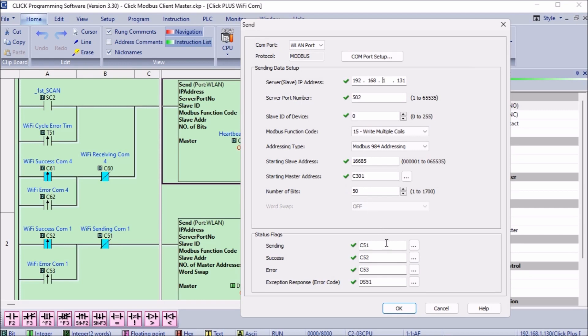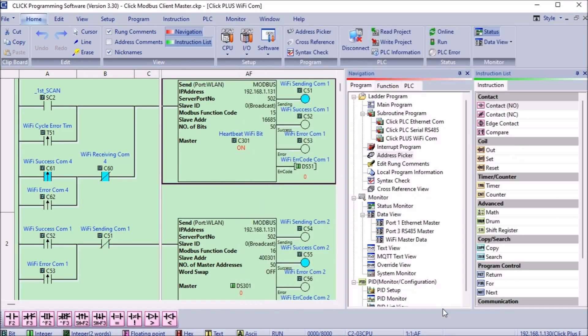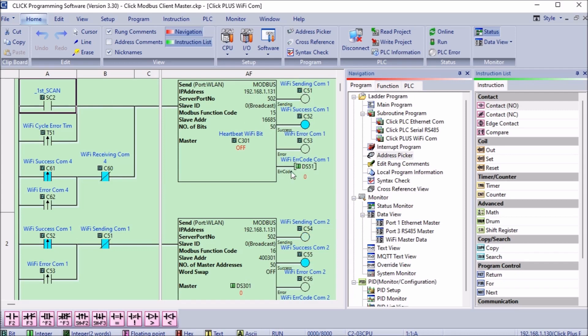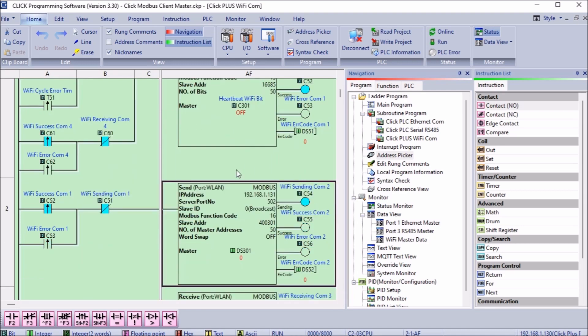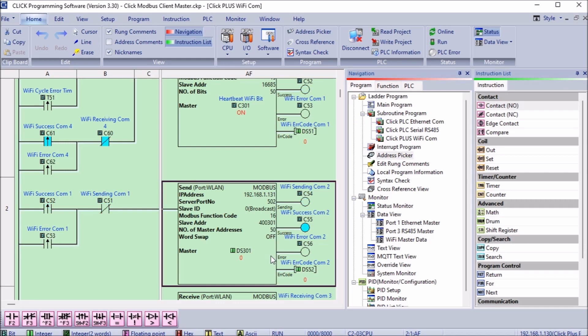Status flags are then set for the send instruction. We will use these for the timing of the communication. The first scan is used on the first rung to send the first 50 bits. The output flags on the first send instruction will trigger the second send instruction. Our next send instruction will use the write multiple registers and the starting address will be 400301 which is DS301 in the CLICK PLC. We will write 50 registers. Registers DS301 to DS350 from the client PLC will be written to DS301 to DS350 of the server PLC.